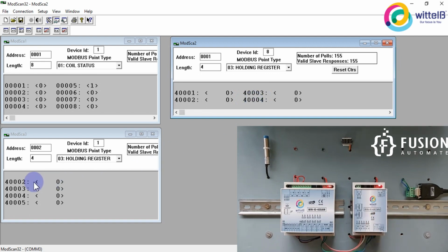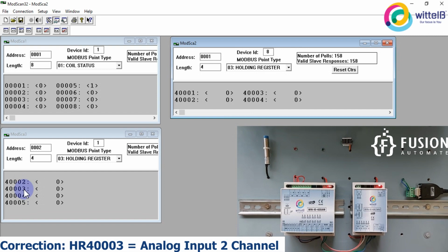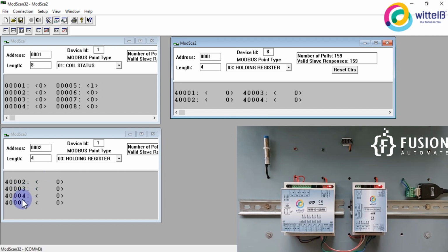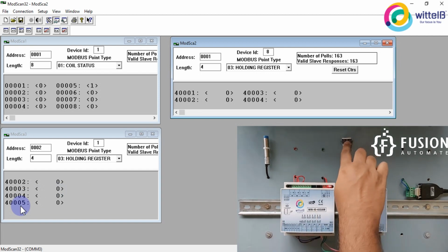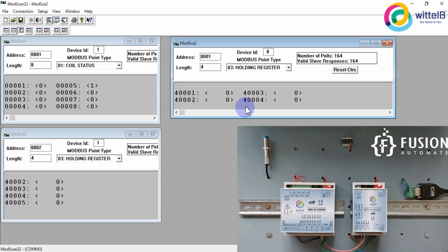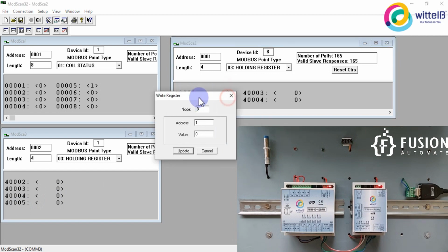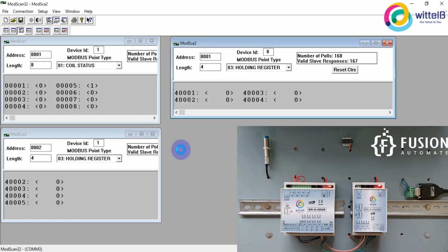Okay, and now here 40,002 is linked with my analog input 1 channel, 40,003 is linked with the analog input 2 channel, 40,004 is linked with the analog input 3, and 40,005 is linked with the analog input 4. Now if I want to turn on this DC voltmeter again, then I have to update the value of my 40,001 holding register.